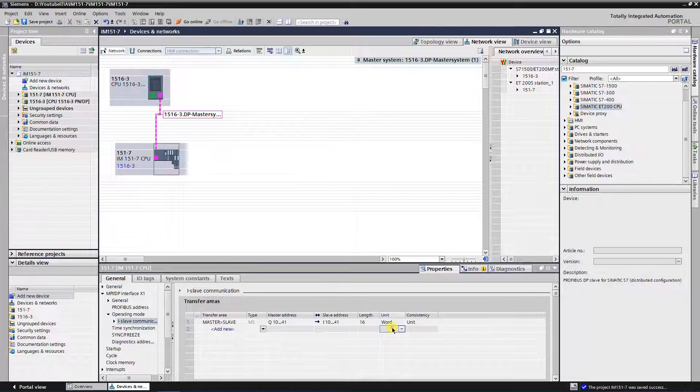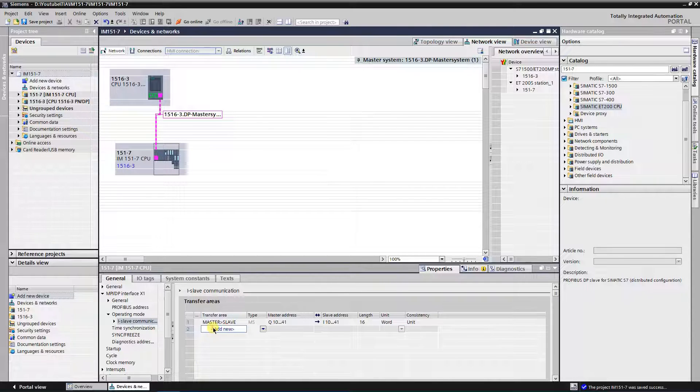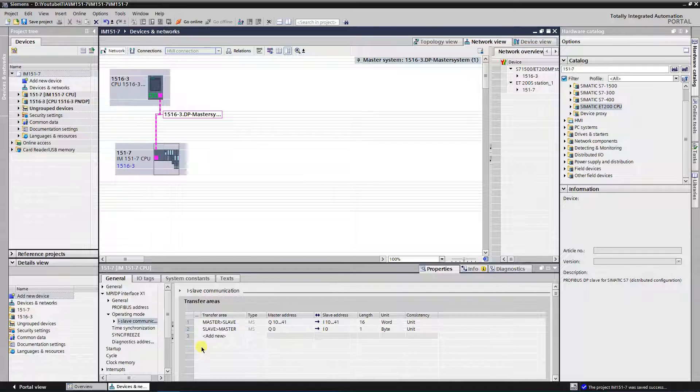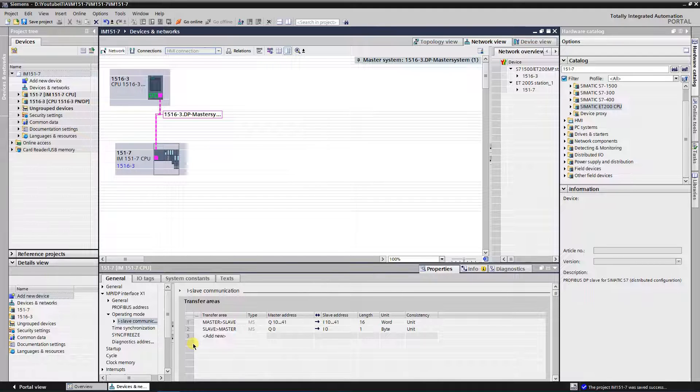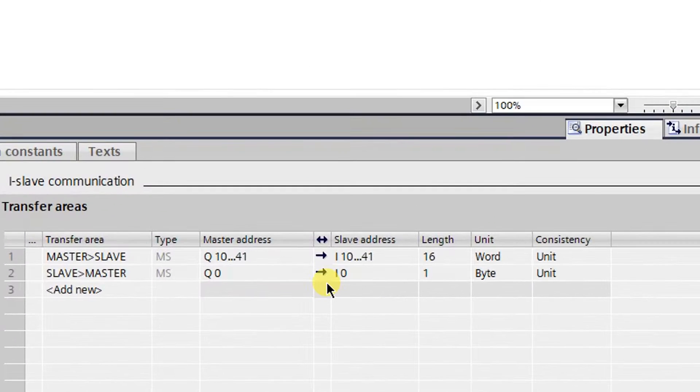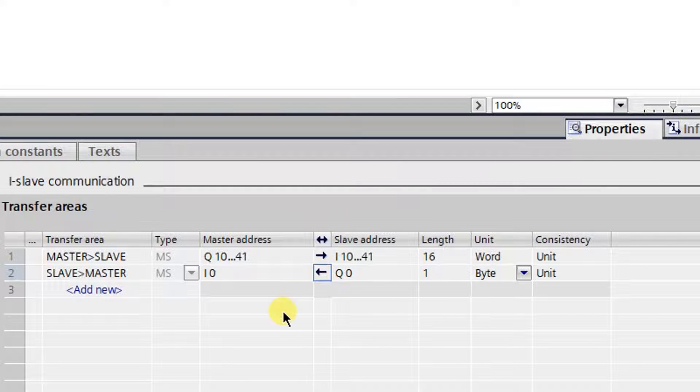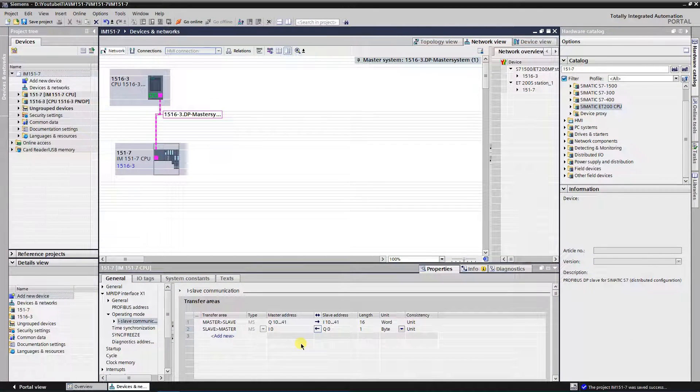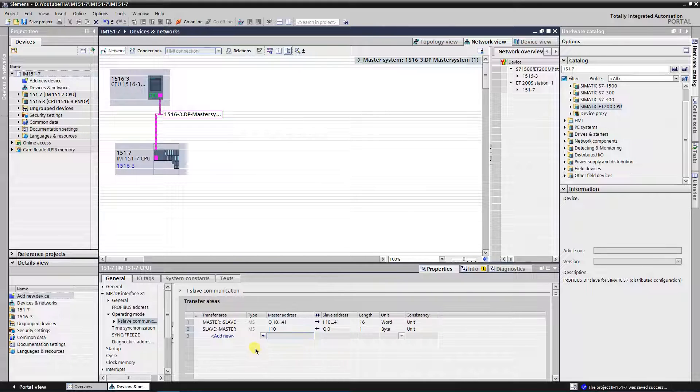Now I need to add one more line, to send data from slave to master. Click on add new in transfer area column. I will name new area as slave to master. This time you must specify inputs on master side and outputs on slave side. To do that you need to change transfer direction. It can be achieved by clicking direction arrow icon once. Now the direction is from slave to master. Outputs can be specified on slave side, and inputs on master side. I will set same 16 words and same numbers for input and output areas.